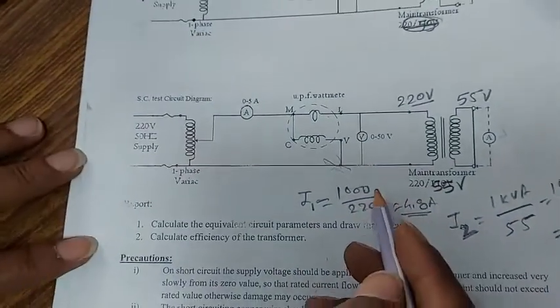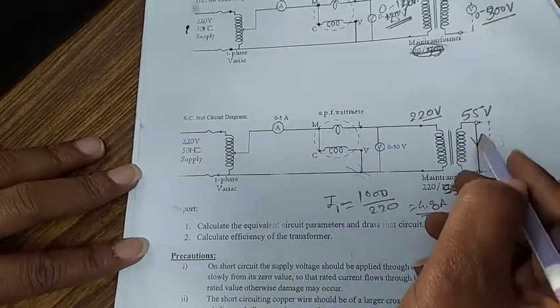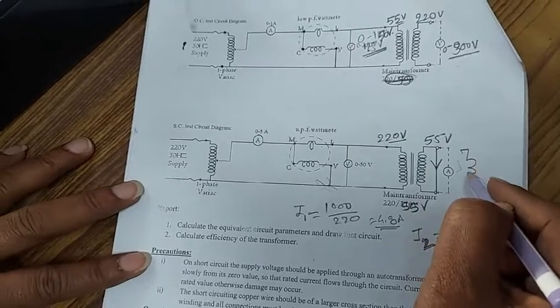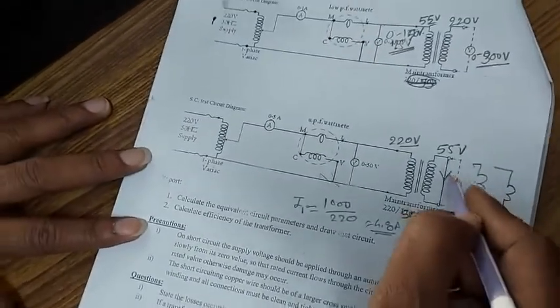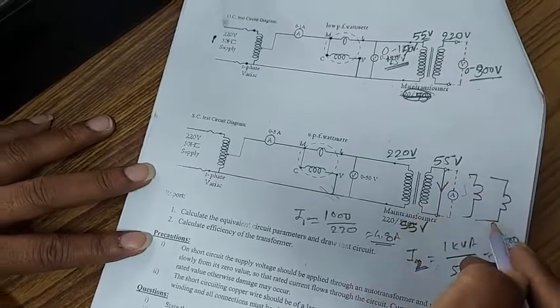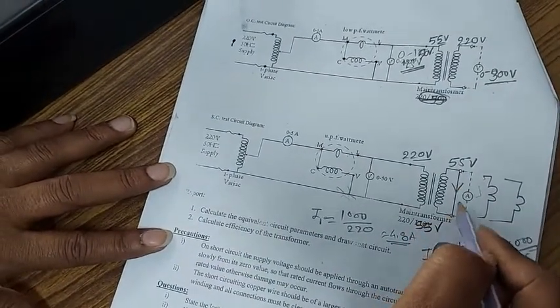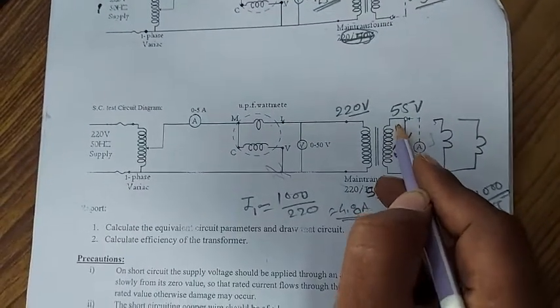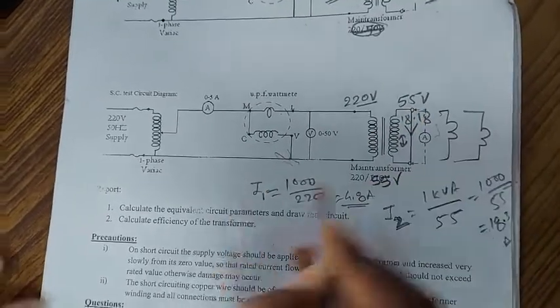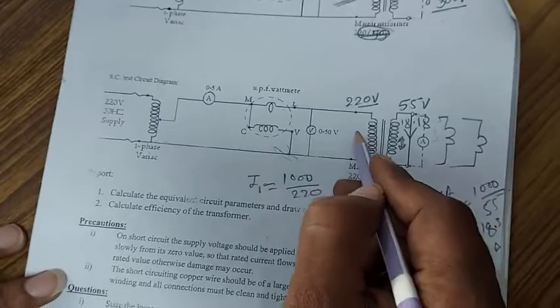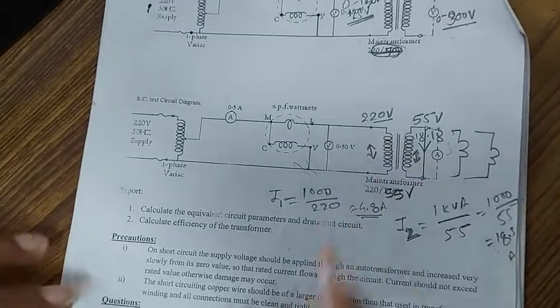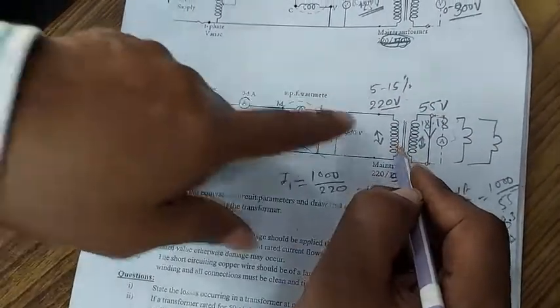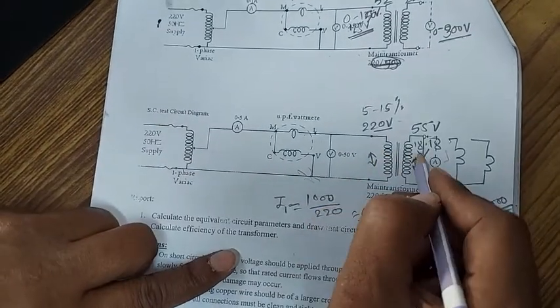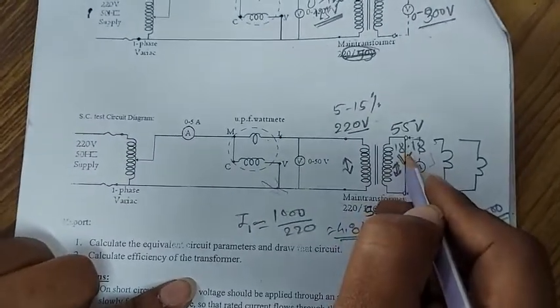Why is that 5 to 15% voltage sufficient to send the full load current through here? Because whenever there will be lamps, there will be loads. But in the short circuit conditions, the lamps will not be there, no load will be connected, so only one small wire will be there which is very less resistance. So very less amount of induced voltage here will be sufficient to send at least full load current 18.18. Now for inducing that small amount of voltage, primary voltage also will be required very small, not the full is required. So that's why 5 to 15% of the 220 volt, that is of that winding rated value, is required to send the full load current through the secondary one.